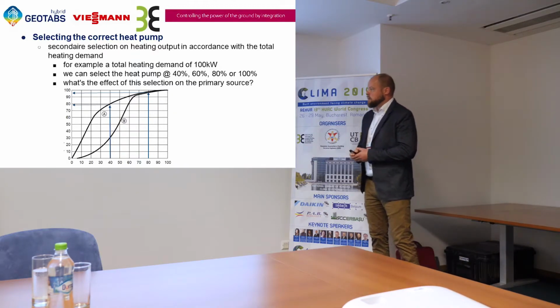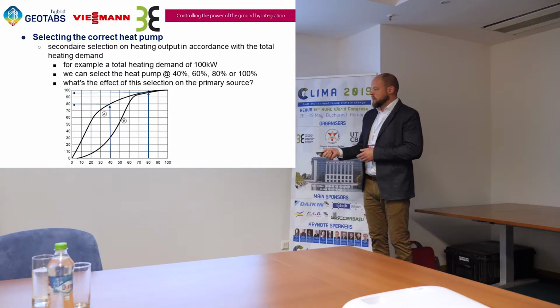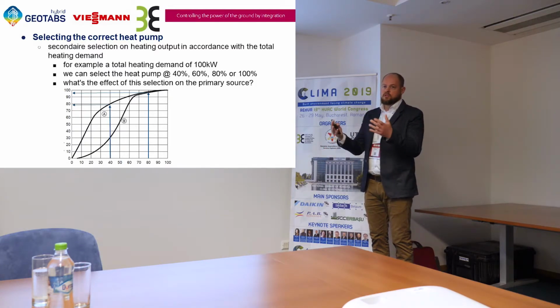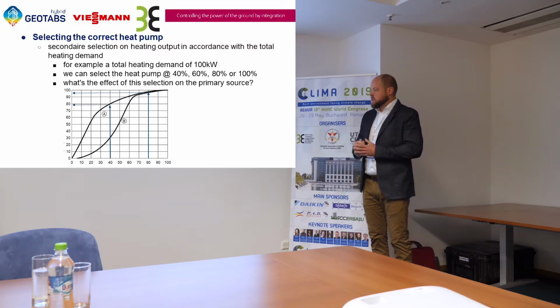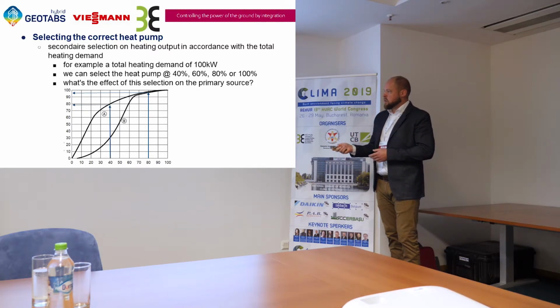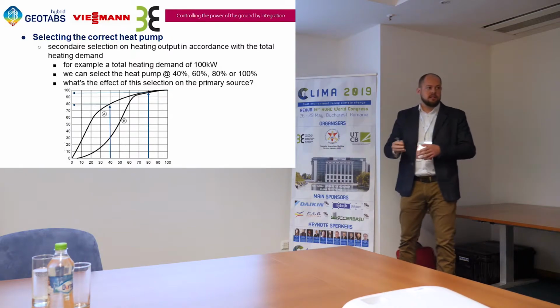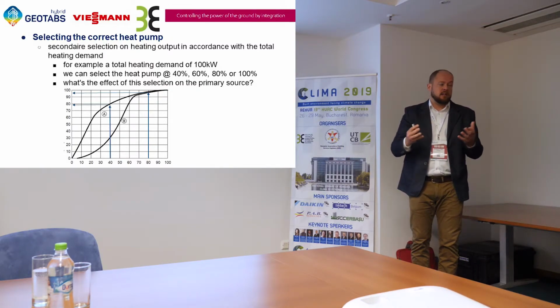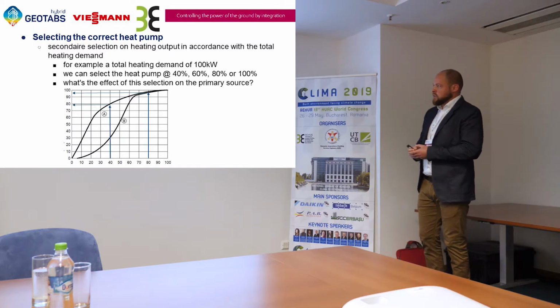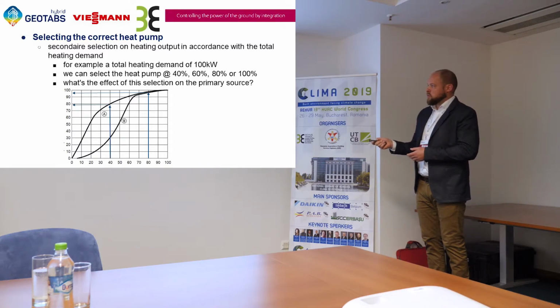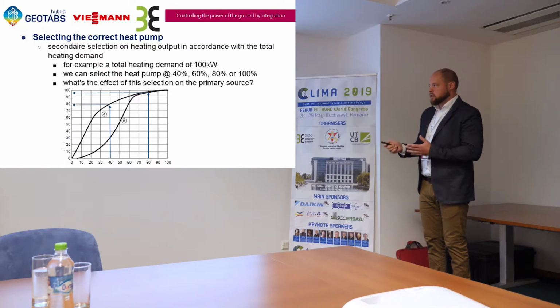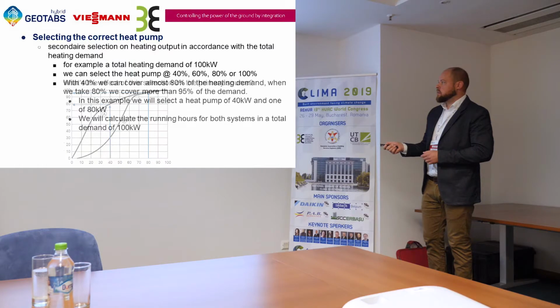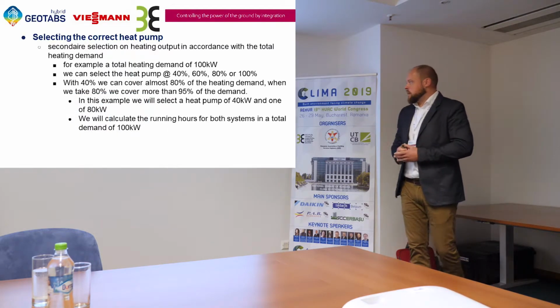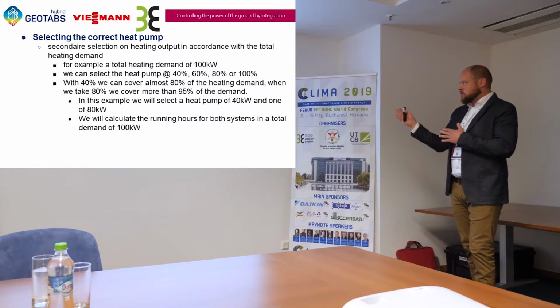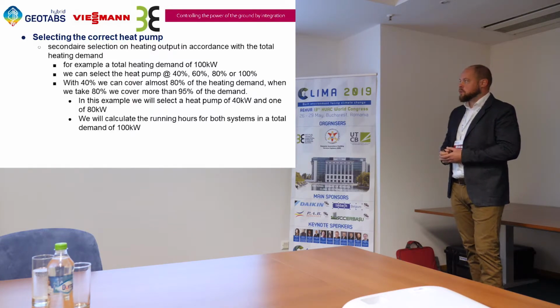Mostly we will work in a parallel condition, and if you see, with 40% of the power, so if the building has 100 kilowatts at -10, for example, with a heat pump of 40 kilowatts, we can cover almost 80% of the total heat load. So that's very much in the total. Even if you go up to 80%, we can almost reach a coverage of almost 100%, so about 96% of the total demanded heat. So I have made a small example, so like the heat pump of 40 kilowatts and 80 kilowatts, and both will be placed in a building with a demand of about 100 kilowatts.